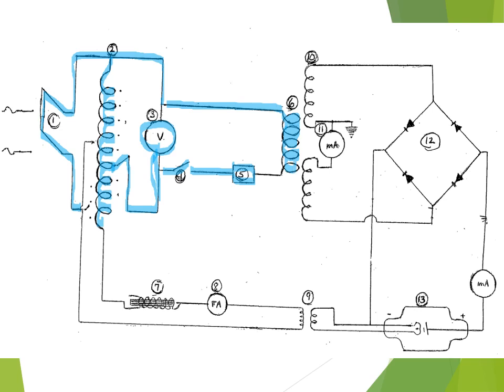Looking at this, this is the primary circuit, otherwise called low voltage. The second part that we have is the filament circuit. The filament circuit is going to continue down from the primary. It's going to include 3 parts, which is not much at all. It includes number 7, which is a MA selector. Part 8 is a filament ammeter, and part 9 is a step-down transformer, and we call it the filament transformer because it's in the filament circuit, and it heats the filament. That's its job. So we're going to write down that this is the filament circuit.